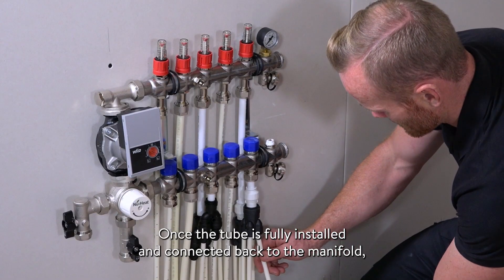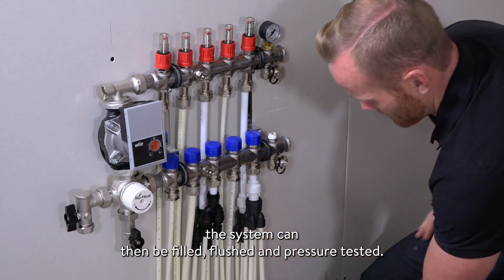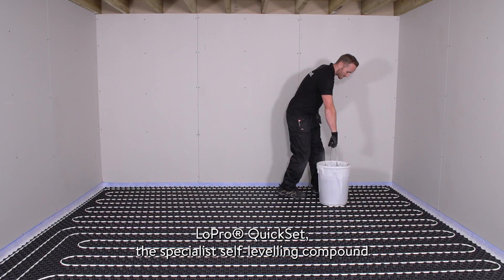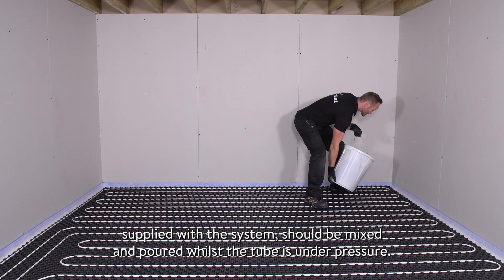Once the tube is fully installed and connected back to the manifold, the system can then be filled, flushed and pressure tested. LoPro QuickSet, the specialist self-leveling compound supplied with the system, should be mixed and poured whilst the tube is under pressure.